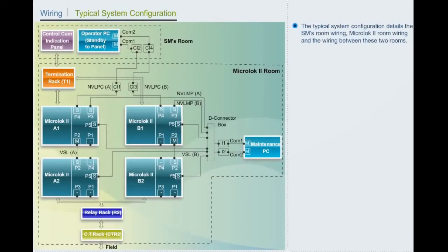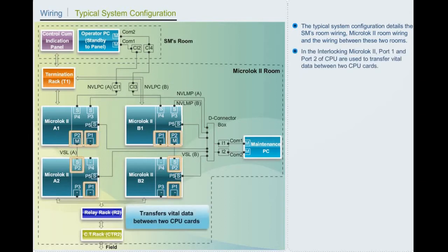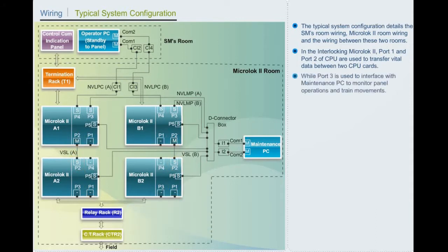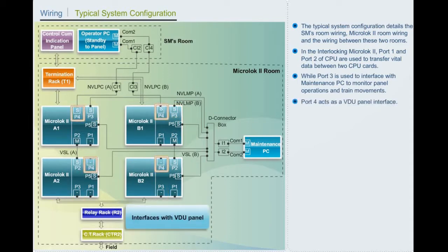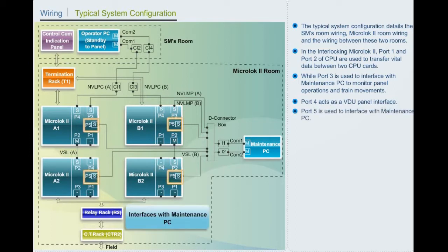Wiring. Typical system configuration. The typical system configuration details the station master's room wiring, Microlok II room wiring, and the wiring between these two rooms. In the interlocking Microlok II, port 1 and port 2 of CPU are used to transfer vital data between two CPU cards, while port 3 is used to interface with maintenance PC to monitor panel operations and train movements. Port 4 acts as a VDU panel interface. Port 5 is used to interface with maintenance PC.